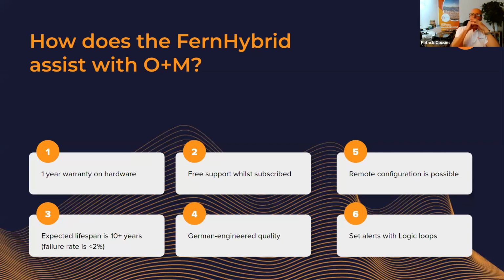Piyush, would you like to take that for a start? Sure. So the Fern hybrid solution is a low maintenance device. It just needs a reliable power supply and internet connection. Even if you do not have internet connection, it can also work without that for some time on the back end. What it does is log the data, monitor the data, and control the devices based on the logic written on that controller, and it is totally customizable. That's the flexibility of the system, that anyone can customize this controller with their own logic. For example, if you want to start the generator at a certain point or time in a day, you can remotely do that without sending anyone to site.